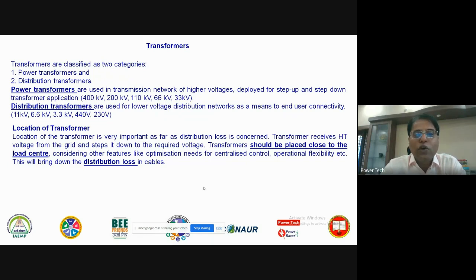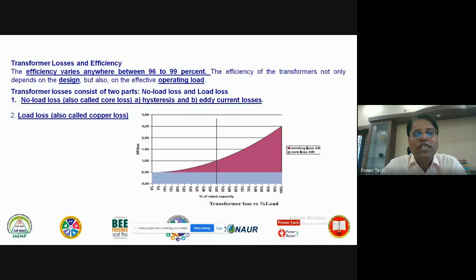You all are stalwarts, good in your domain and good electrical engineers. You know all these things. So, two types of transformer: power transformer and distribution transformer. You know that a transformer should be placed close to the load centers to reduce the distribution losses. And there are two losses basically: no load loss, which is also known as core loss, hysteresis or eddy current loss, and also load loss, that is the copper loss.